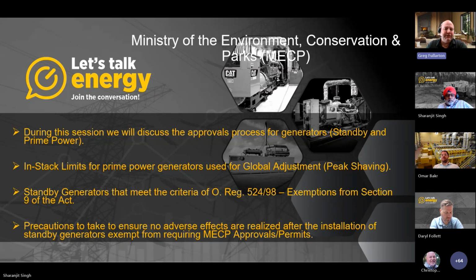During this session we'll discuss the approvals process for generators, both standby and prime power. We'll talk about the in-stack limits for prime power generators used for global adjustment — those require approvals regardless, completely independent of standby generators. Standby generators can only be tested, I believe, for up to 60 hours in a year before they start to fall out of the standby power rating. Standby generators that meet the criteria of O. Reg. 524/98 — you're going to hear that a lot.